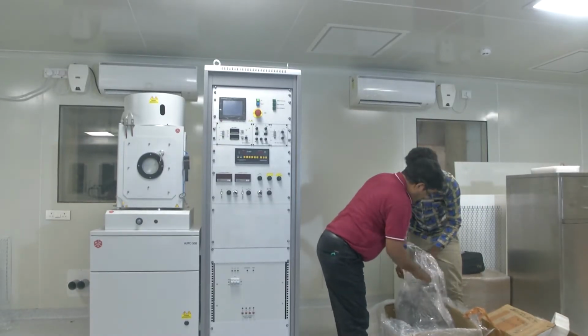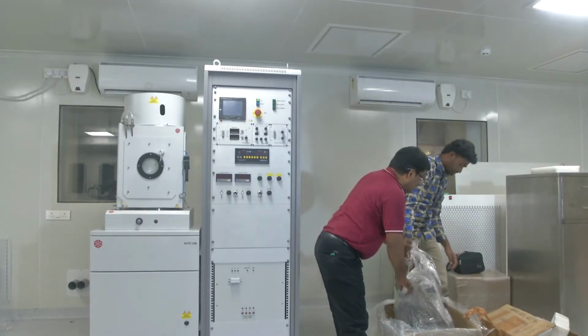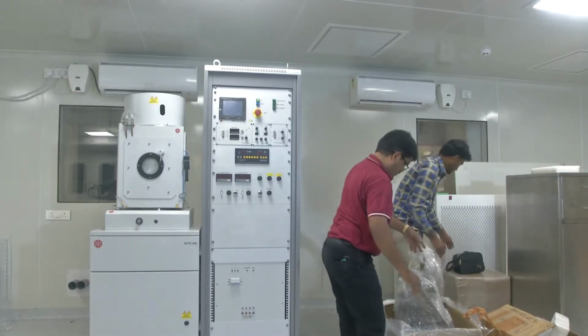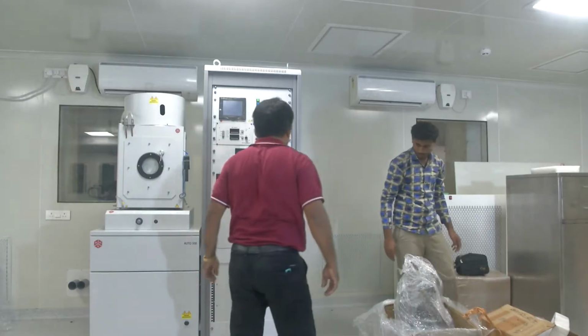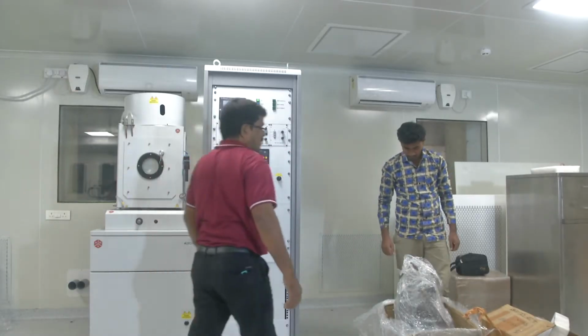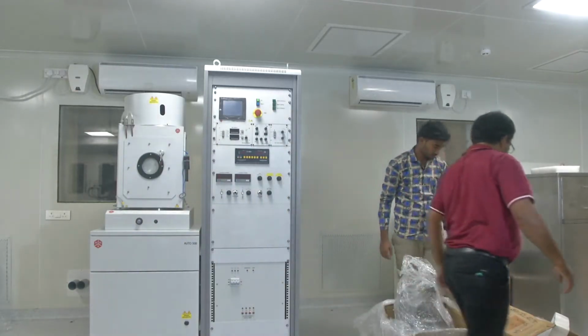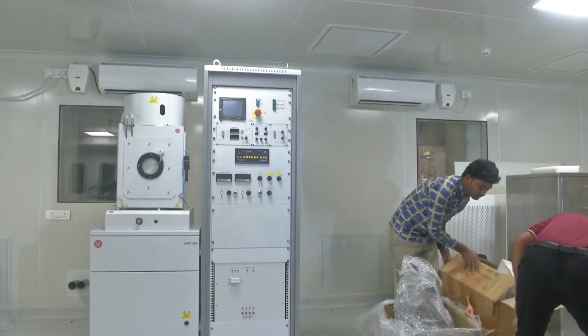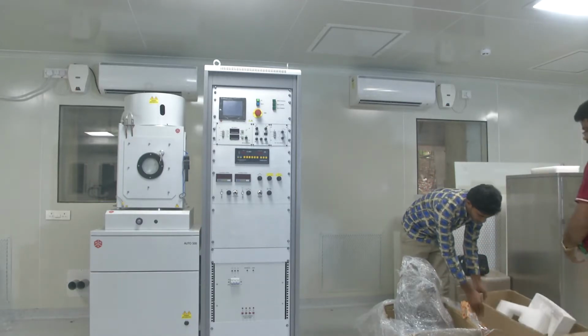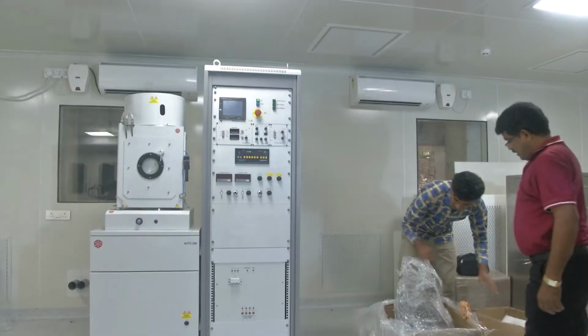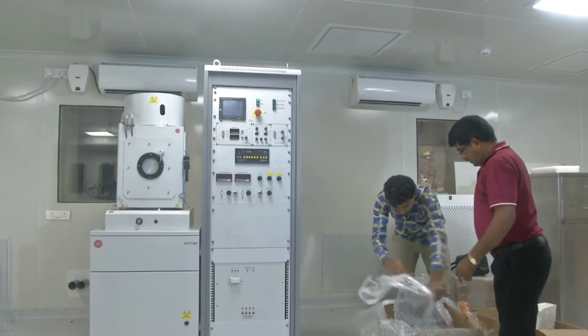With regard to safety purposes, chiller, compressor, gas cylinders, everything should not be kept inside the lab. So what we will do is, we will take these units, and we have a utility room that is made outside the lab with connections coming into the lab. So after it is unpacked, the equipment will be taken out into the utility room, and connections will be taken from there into the system.